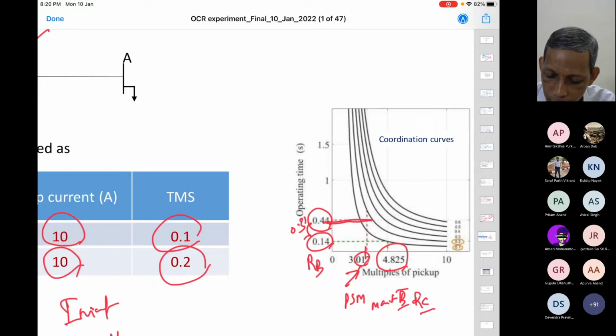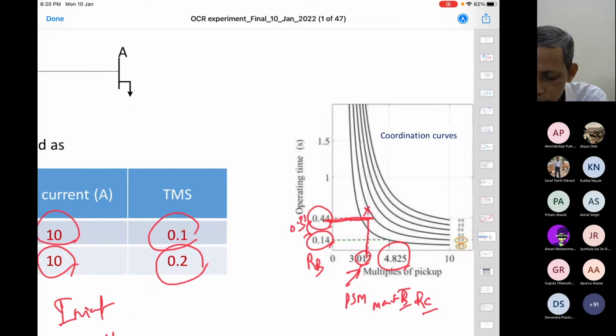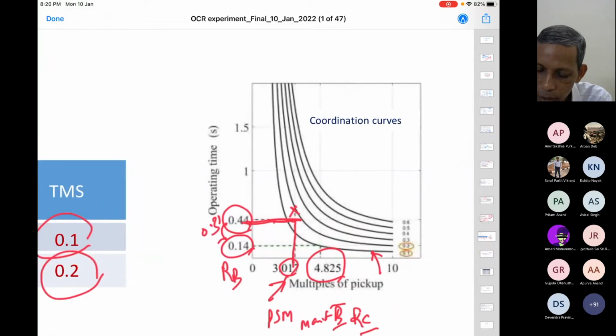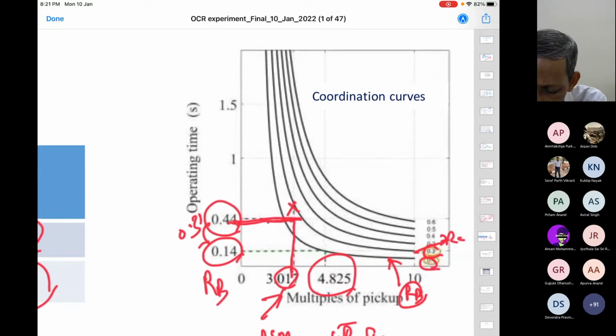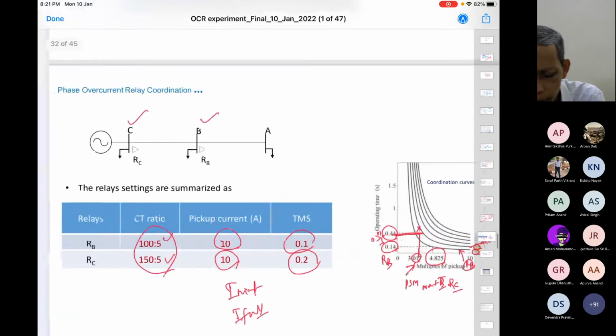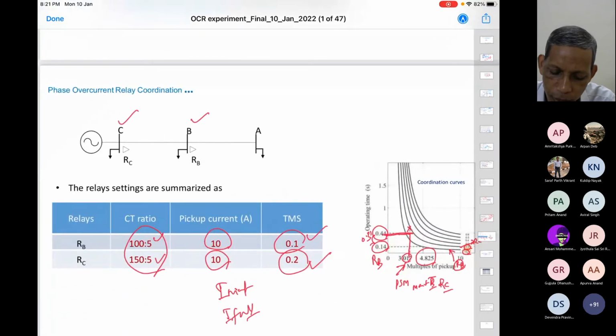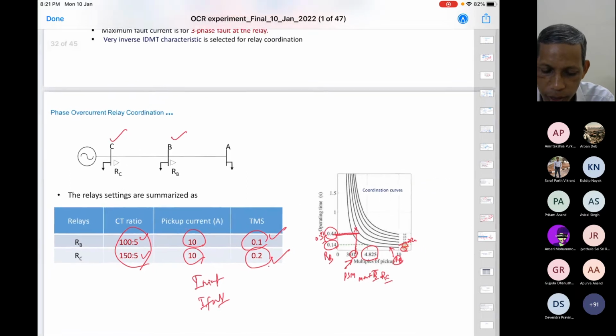So you got this one, and you get the corresponding intersection of these two. If there is no curve at that point, we take the next curve. Okay? If you see, the lowest curve is assigned, as I already mentioned, to the extreme end relay RB, and the next curve goes to RC. So here we get 0.1 and 0.2. As per the reliability, this is 0.1 TMS for RB and 0.2 TMS for RC. This is what we do in terms of this coordination perspective.